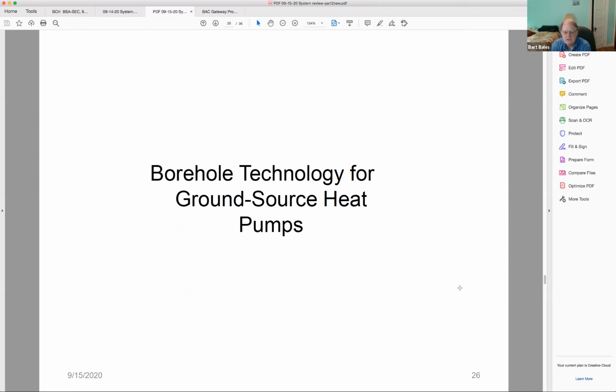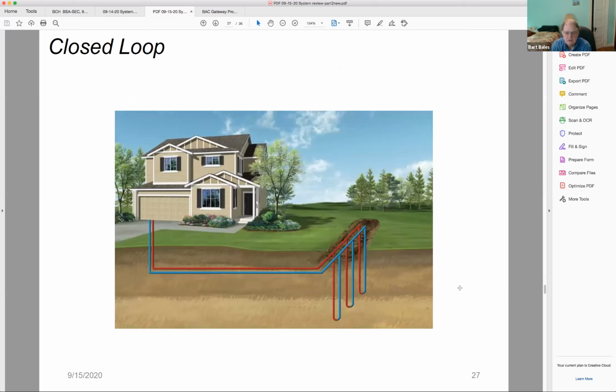Okay, borehole technology. There's been talk about doing ground source things out under the plaza somewhere. That means you drill boreholes down into the ground, and they'd typically be 300 to 500 feet deep. Then you run water down into the ground and back up, and then you use the heat pump to take energy from the water. The water that you're getting from the ground might be 45 degrees, but the heat pump essentially allows you to upgrade that to temperatures that are usable for heating a building, up to 120 degrees.